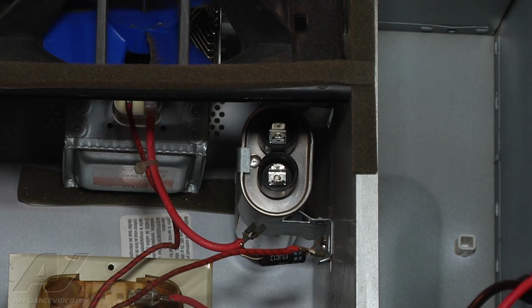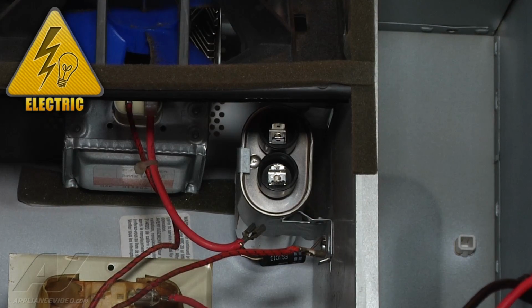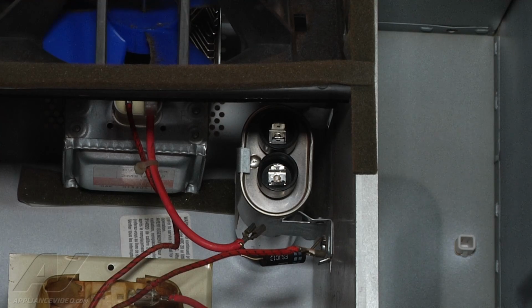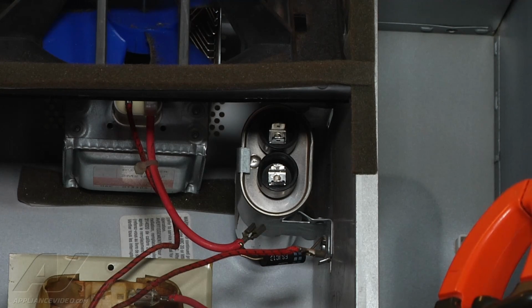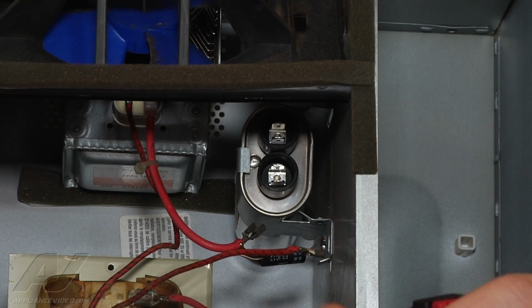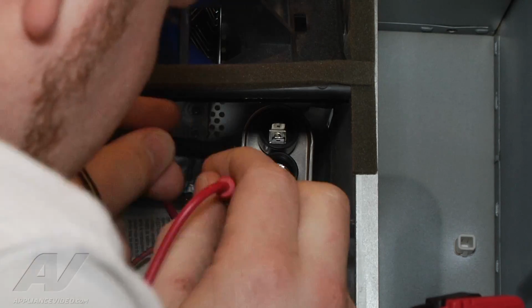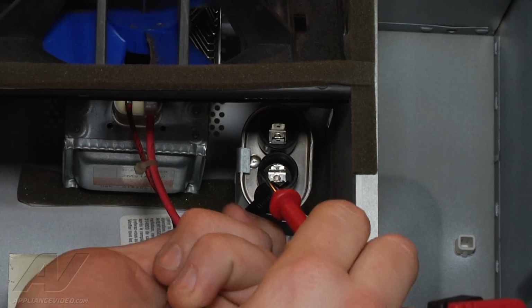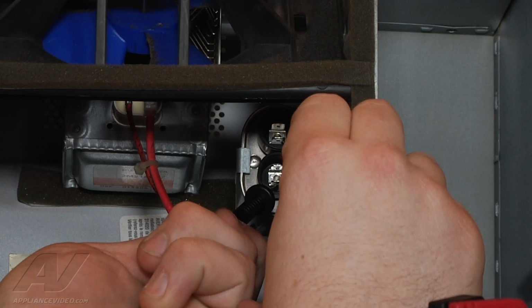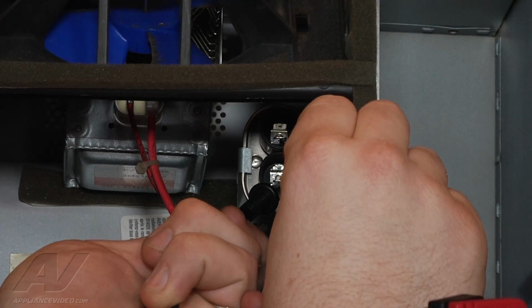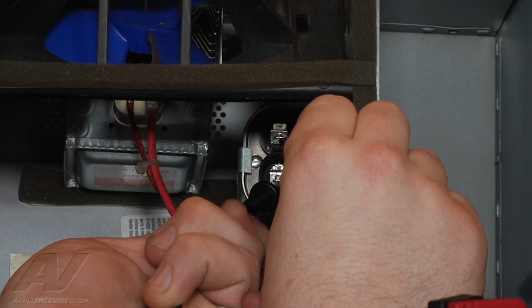But what we'll do then is test our capacitor now, and of course you want to discharge the capacitor again after we had power applied to it and ran the test. Make sure you discharge the capacitor again. And to test it, I have a digital meter here, and it's a little different from a digital to an analog meter. On this one, we're going to put it on the DC voltage setting. And when we hook our meter leads onto the capacitor here, we should see a spike or a jump in the reading on our meter here.